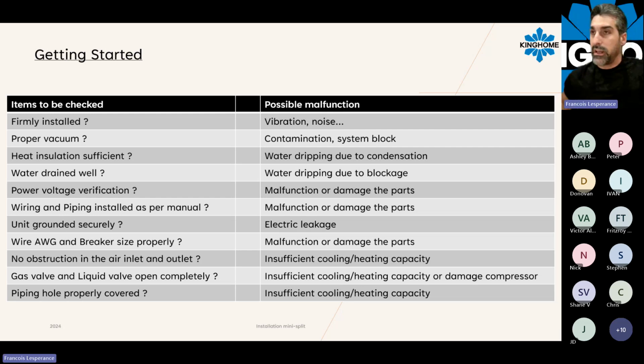So what's really important, when you have done all your service portion on the systems, or a brand new installation or replacement, whatever, it's always good to have a small checklist with you and make sure everything is installed correctly as per manual. You don't have any vibration or noise coming from the unit. You have performed a proper vacuum, so you avoid contamination or system blockage. Your insulation is sufficient, like make sure you don't have a gap in your insulation, so condensation can occur and have some water dripping. You have tested your drain well also. Make sure there's no remaining water in the drain pan.